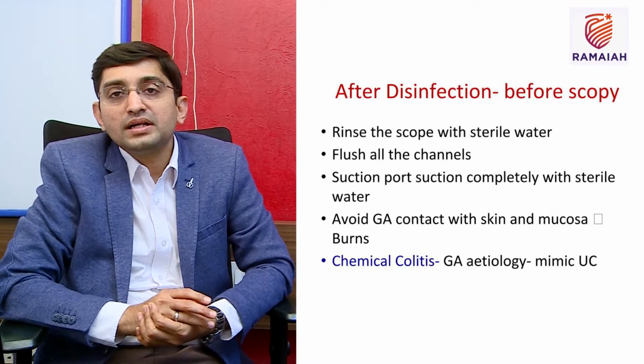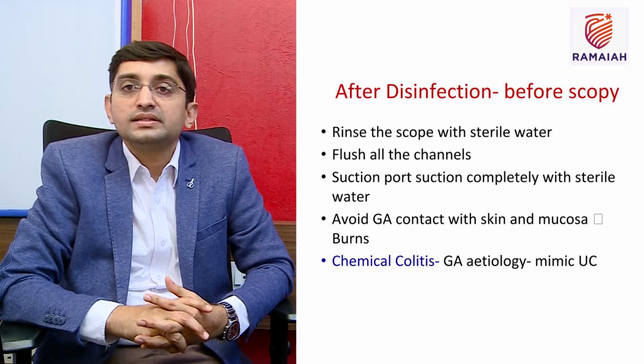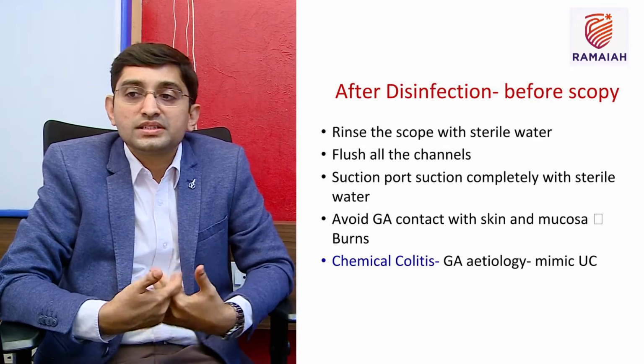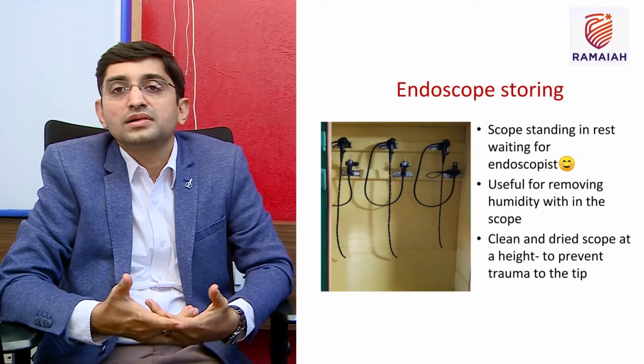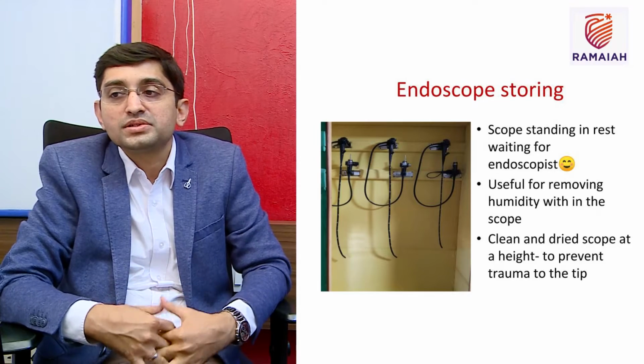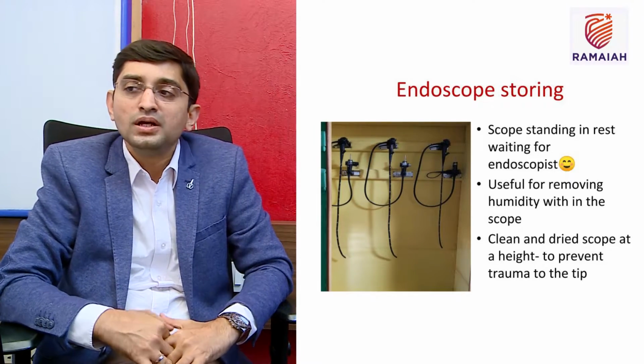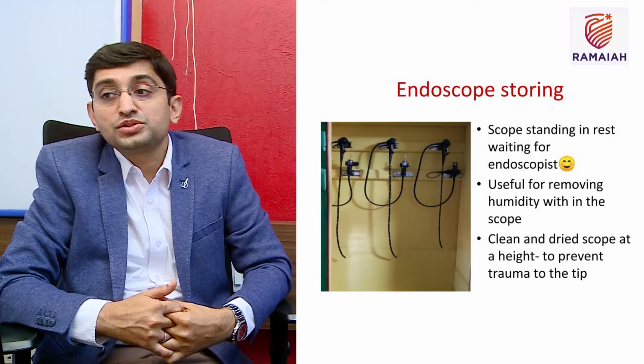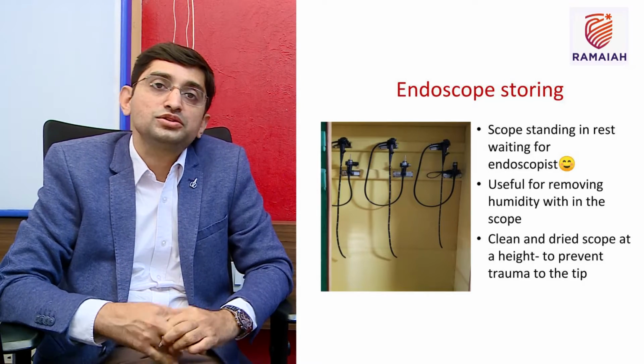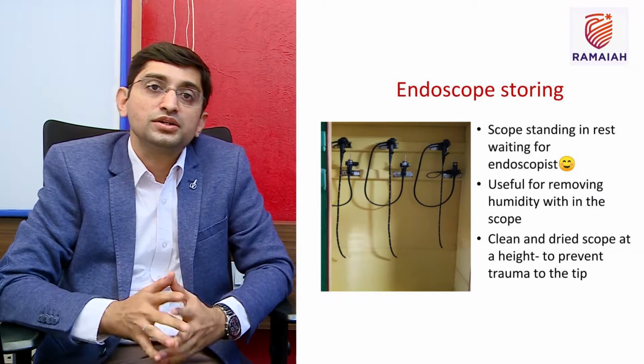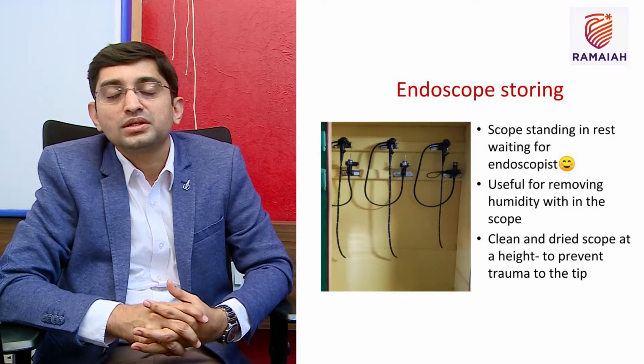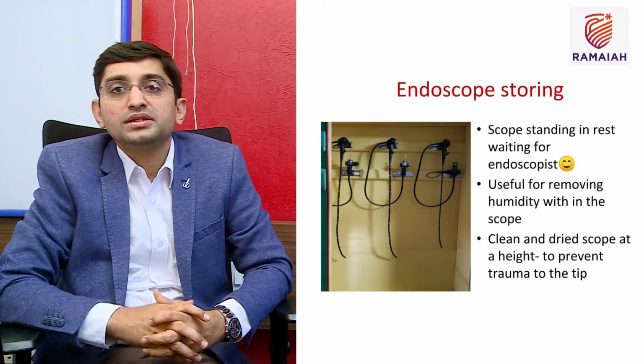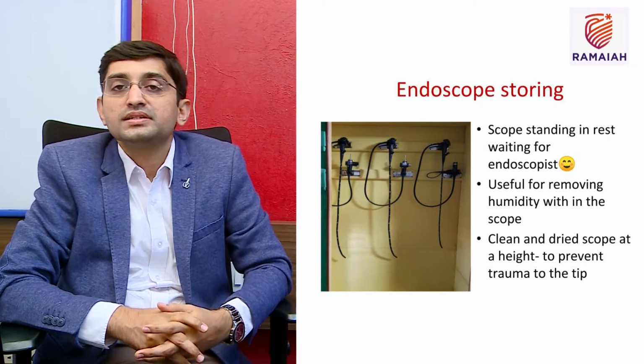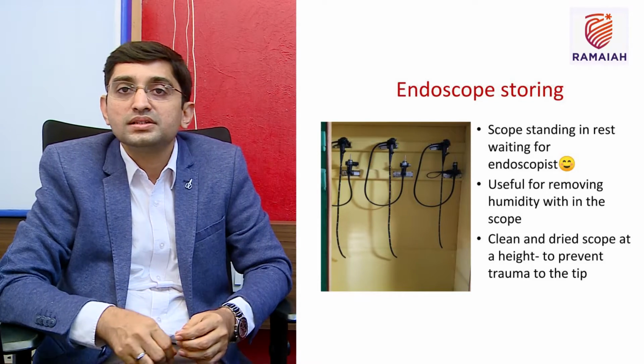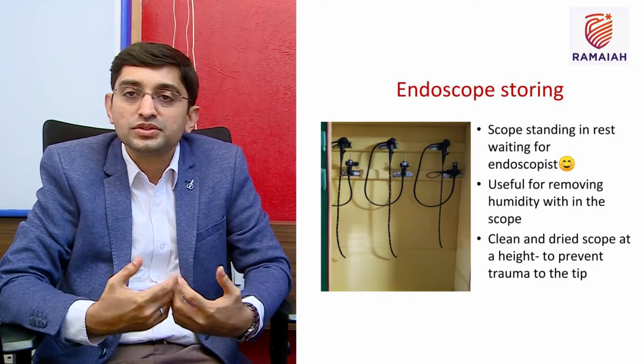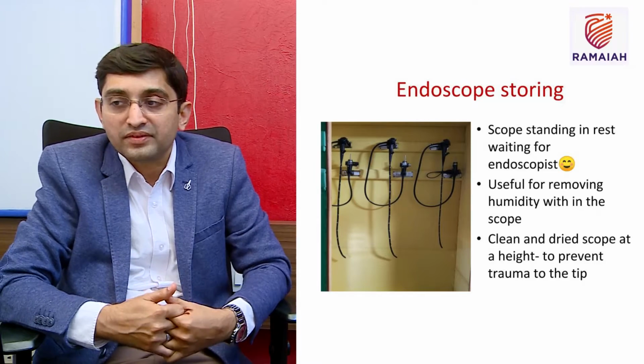Once we say that the endoscope is completely clean, disinfected, and useful for the next person, we should always, after completing all the procedures, store the scope. Endoscopes should always be stored in a standing position, because the endoscope waits for the endoscopist. The advantage of the standing position is that it removes all the humidity. Even if there is some amount of water within the channel, it is going to fall down because of gravity.